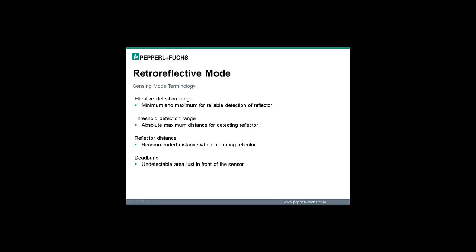Common terms used with retroreflective sensors: effective detection range is the minimum and maximum distance for reliable and consistent detection of a reference reflector — the recommended range that the sensor and reflector should operate within. The sensor's threshold detection range is the absolute maximum distance for detection of a reference reflector; operating in the threshold detection range is not recommended as many external factors can cause the sensor to no longer detect the reflector. The reflector distance is the recommended minimum and maximum distance from the sensor face when mounting a reflector. The deadband is the area just in front of the sensor face in which the sensor cannot reliably detect the reflector because of the emitter-receiver separation and the angle at which light is reflected back.